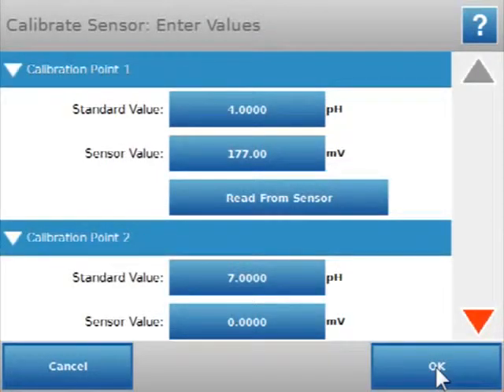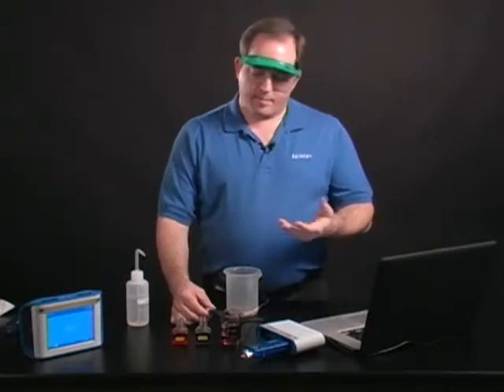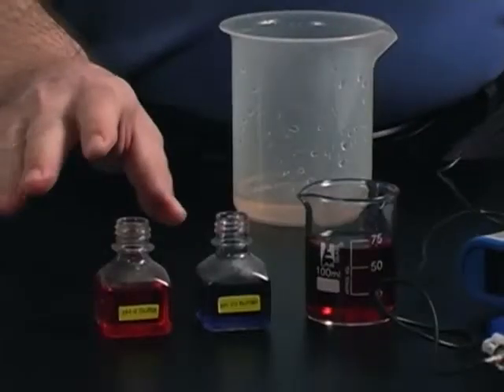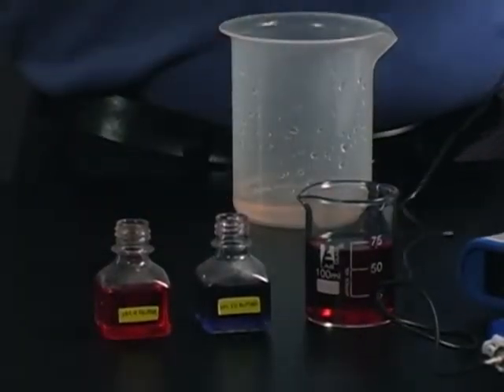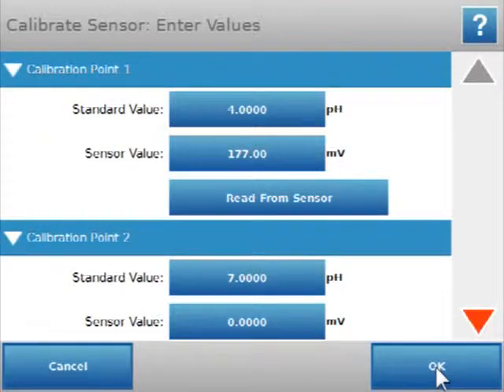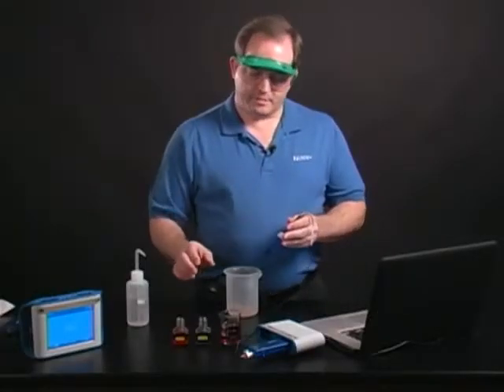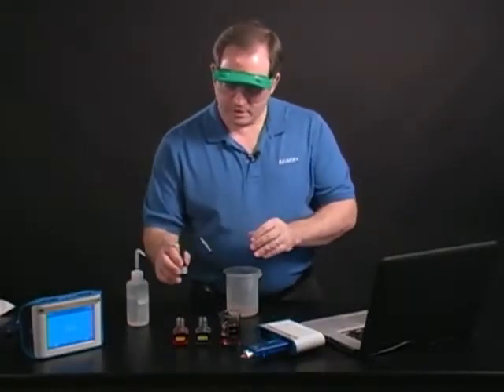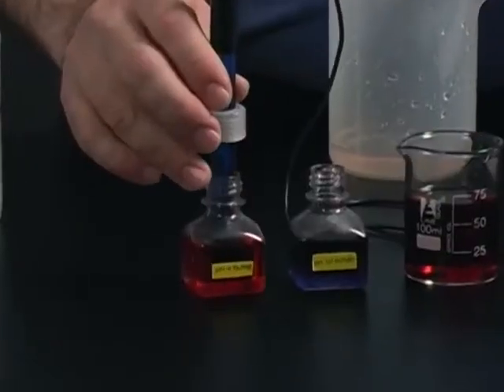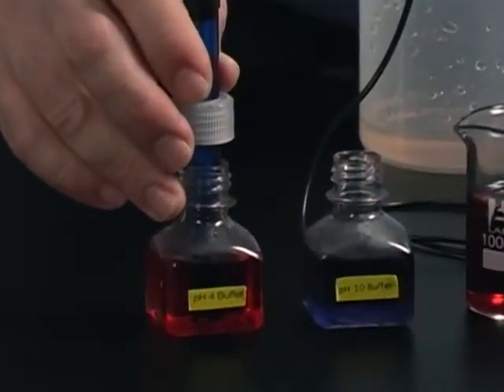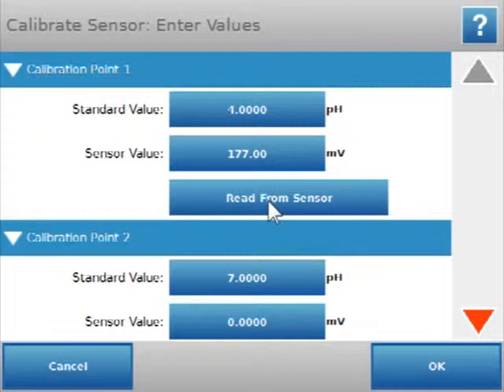You'll see it automatically comes up with the 2 points shown. I'm using a 4 buffer and a 10 buffer. You'll see it's set up with 4 and 7 by default, but we can change that. So I'm going to start off with my 4. I'm going to take the probe and stick it into the 4 buffer, and I'm going to hit the read from sensor. And that's going to take a value from the sensor, and it's going to associate that with pH 4.